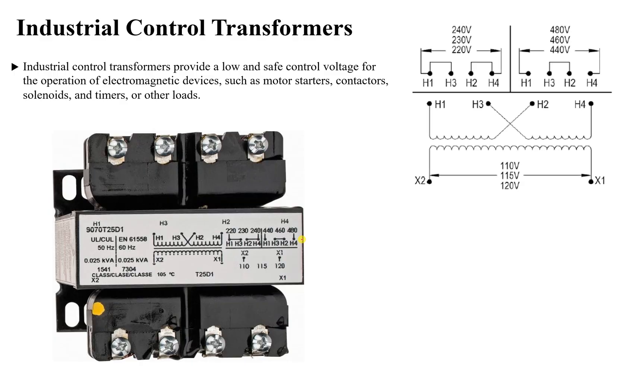This configuration is similar to the first, just with a different wiring arrangement, to obtain the same output. For example: 110/115/120V output — if you have 240V or 480V input and use these two configurations, you get 120V. With 460/230V you get 115V, and with 440/220V you get 110V.